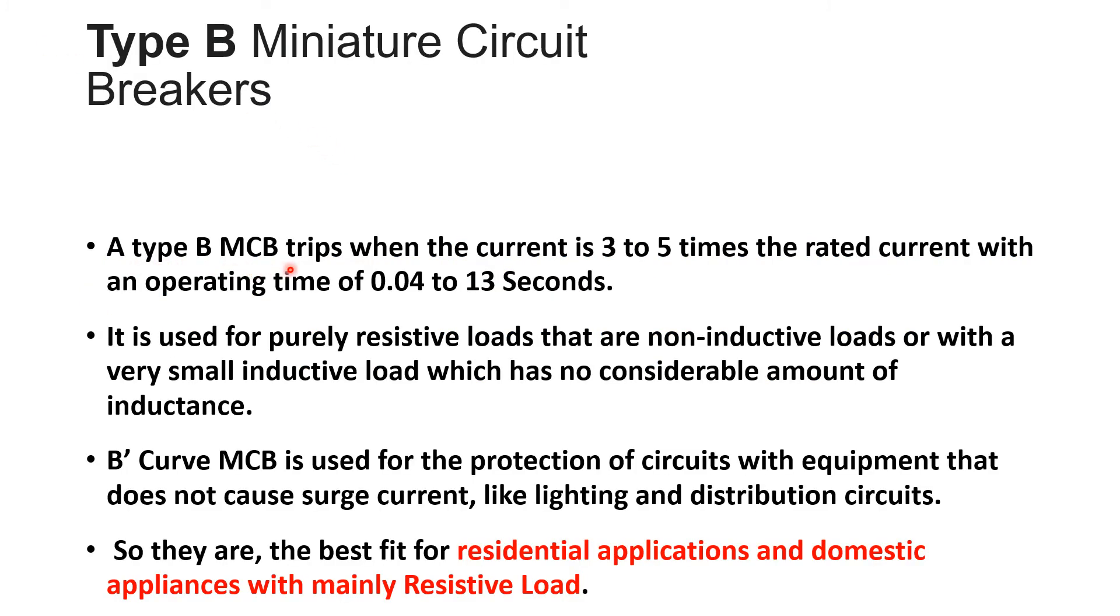A type B MCB trips when the current is 3 to 5 times the rated current with an operating time of 0.04 to 13 seconds. So what we are going to see in our experiment we are going to check the same thing as our MCB of rating 6 ampere. It is B type characteristic. So this particular MCB whenever current reaches 3 times to 5 times of its rated value, so 3 times means 18 ampere to 30 ampere in that range, then that particular MCB will trip within 0.04 to 13 seconds. So if it operates within this period it means your B curve MCB is okay.